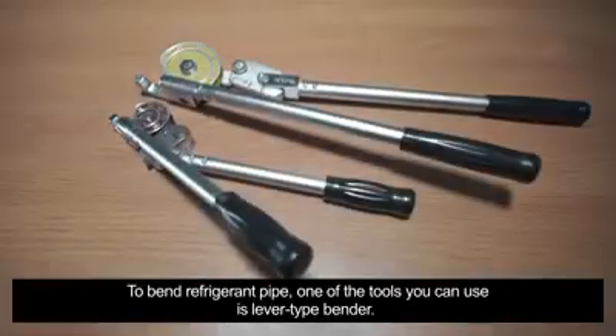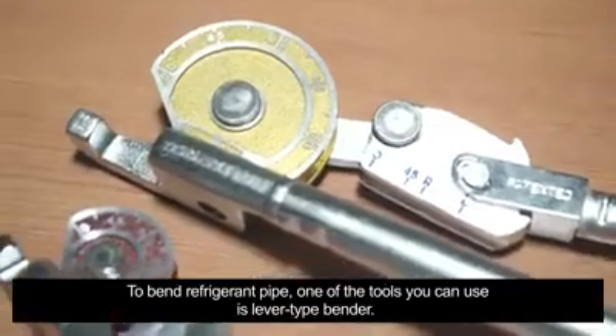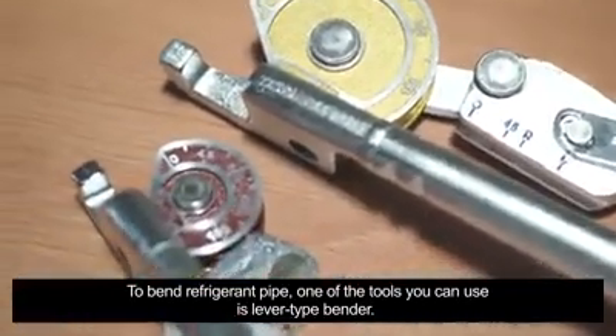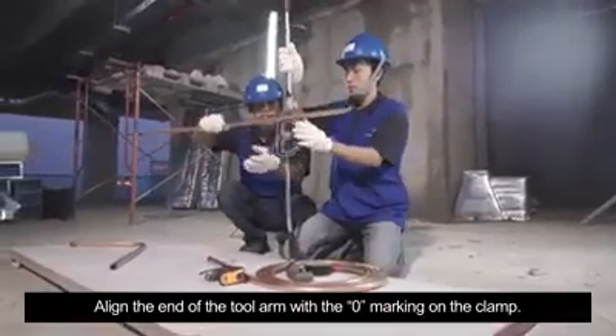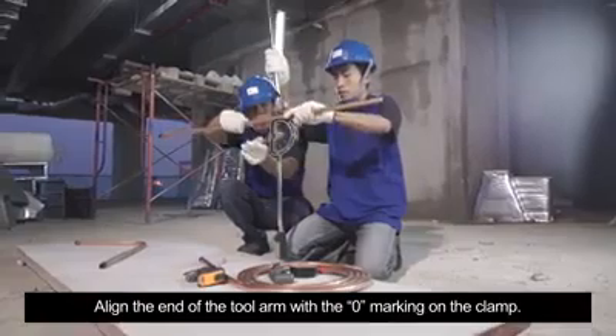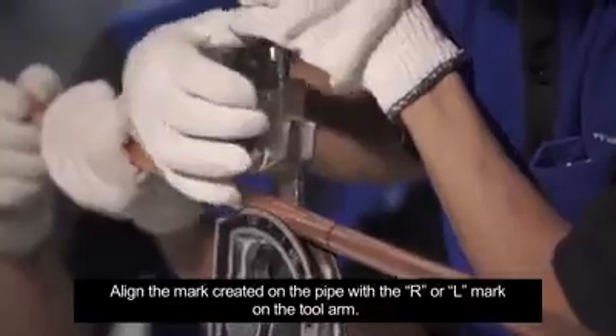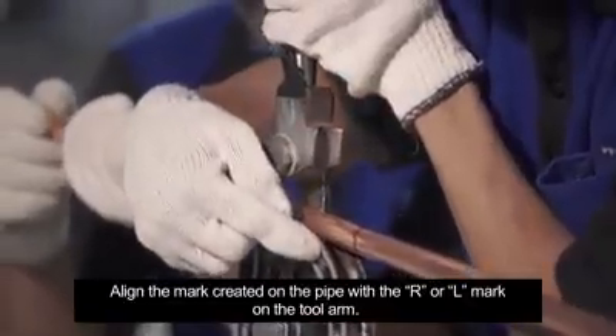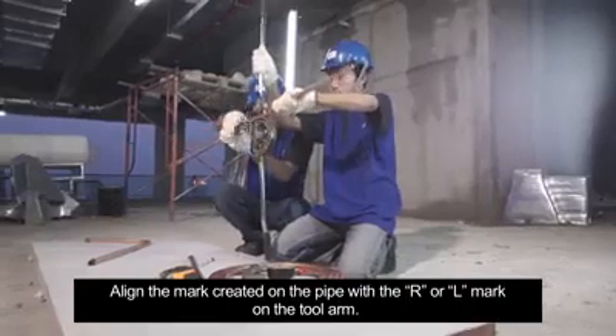To bend refrigerant pipe, one of the tools you can use is lever-type bender. First, mark the part of the pipe to be bent. Align the end of the tool arm with the 0 marking on the clamp. Align the mark created on the pipe with the R or L mark on the tool arm.